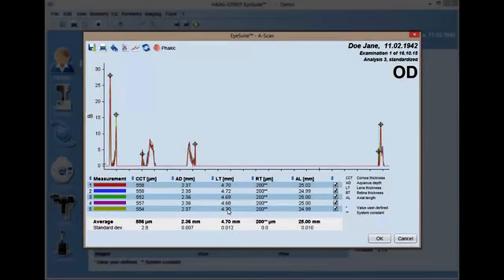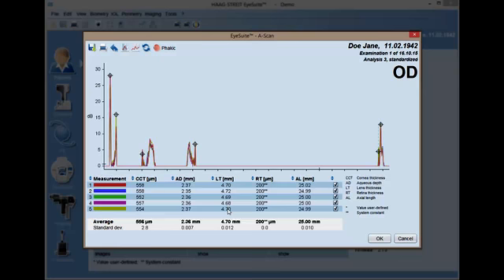To manually adjust the length gates along the A-scan, it is strongly suggested that the user magnifies the area intended for manual adjustment.